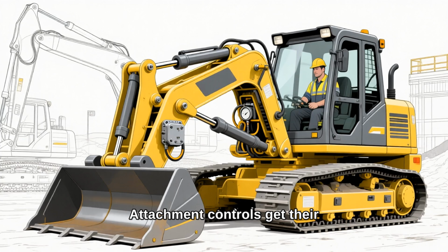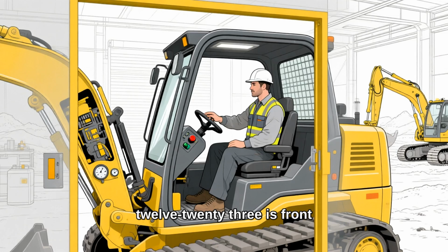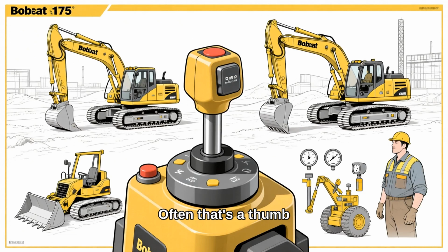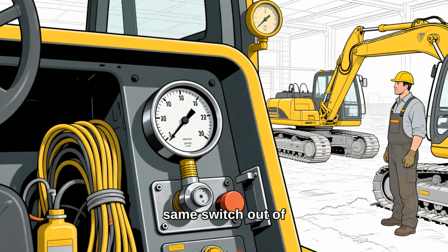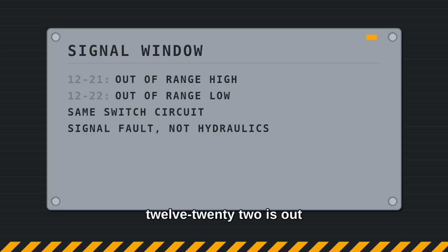Attachment controls get their own group, and they fail in the most annoying way possible. 1223 is front auxiliary PWM switch not in neutral. The loader won't start something it thinks is already commanded. Often that's a thumb switch resting slightly off-center, or a return spring that's gotten lazy. 1221 is that same switch out of range high. The signal came back stronger than the controller permits. 1222 is out of range low. The other side of the same window. Both point at signal, not muscle.